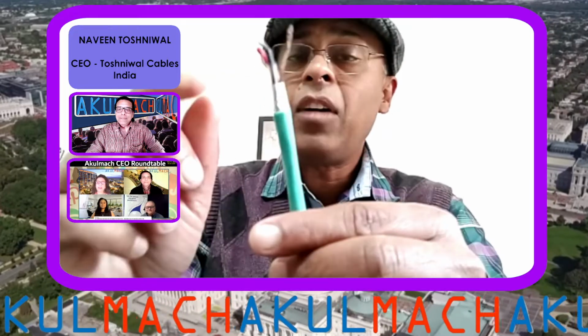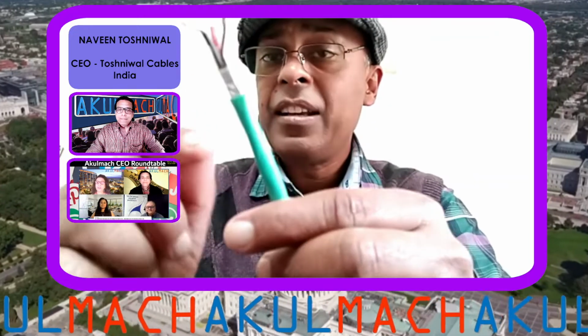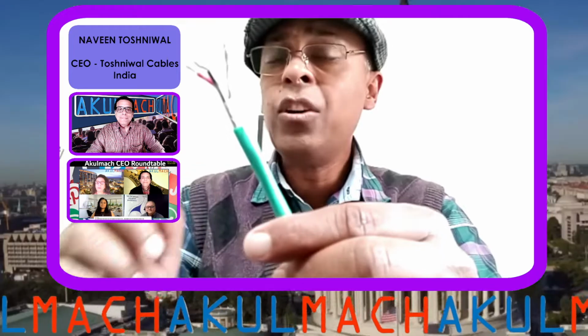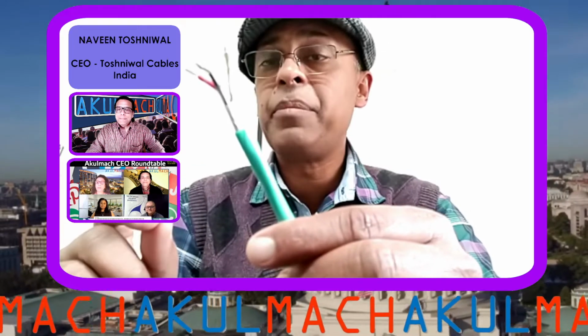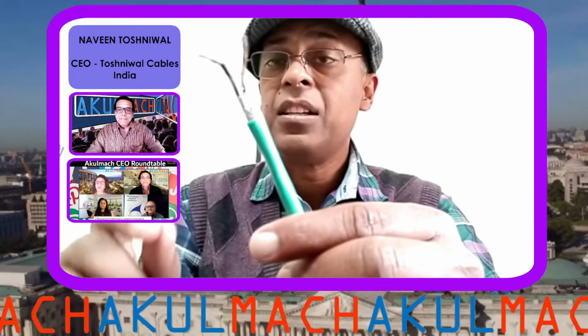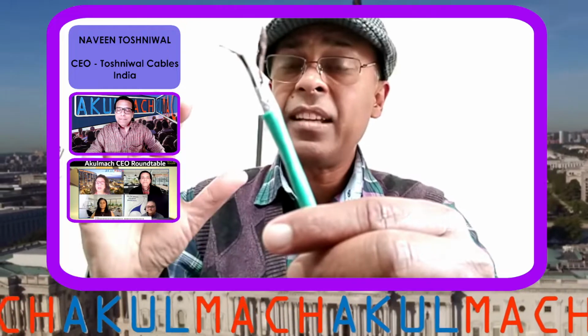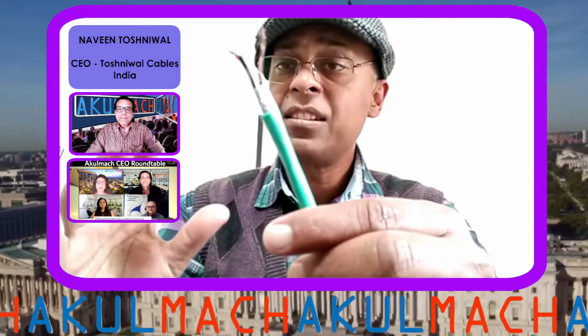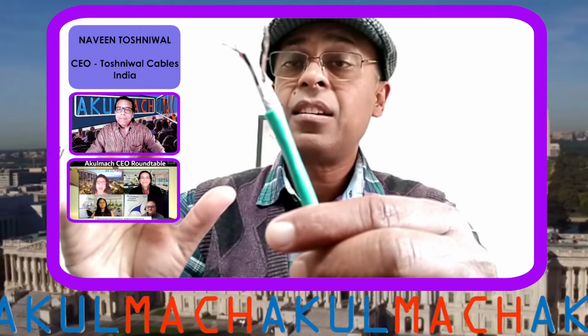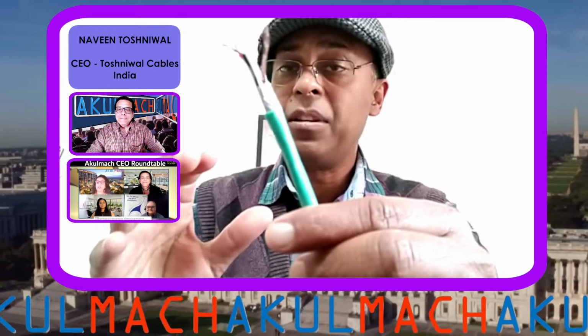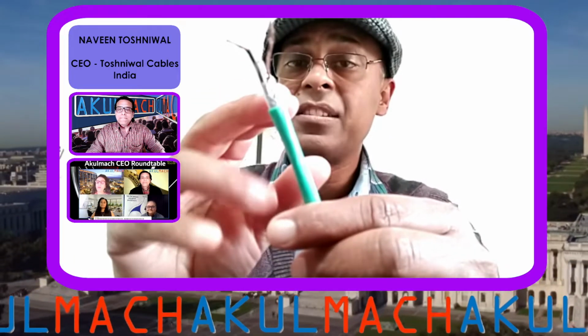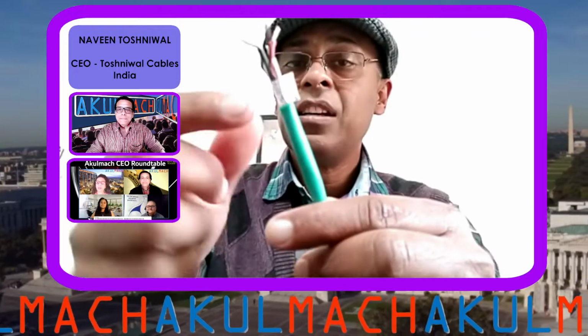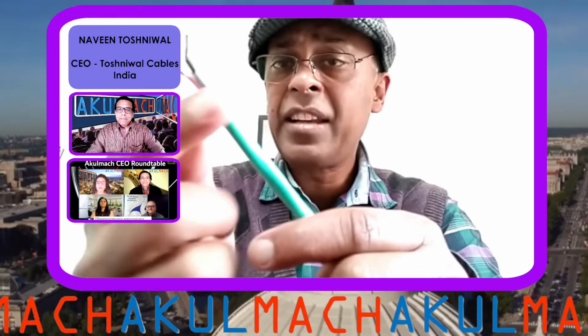Now I will go to the next point. This cable carries a very low voltage, say maybe 4 millivolts or even lower. So there are chances that electrical interference from outside, from other cables, might penetrate inside and disturb the signals. So you will see there is a metallic tape given over here.